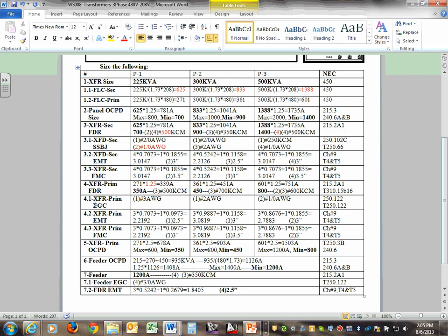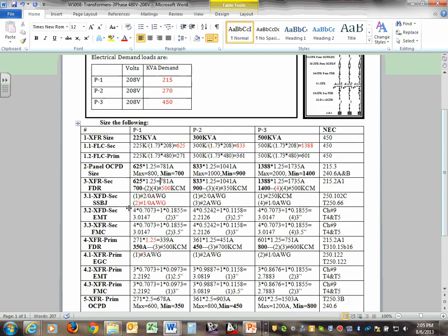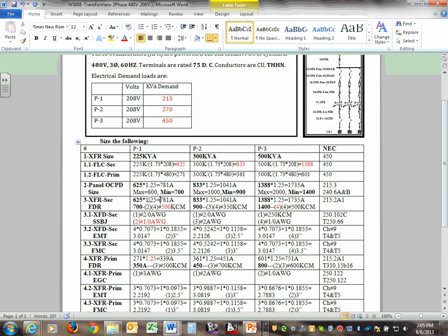Yep. You can, under one rule. There's a tap rule for transformers. If you stay within 10 feet, then you can.